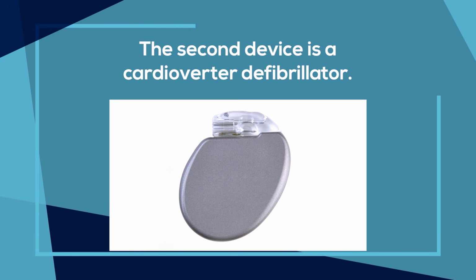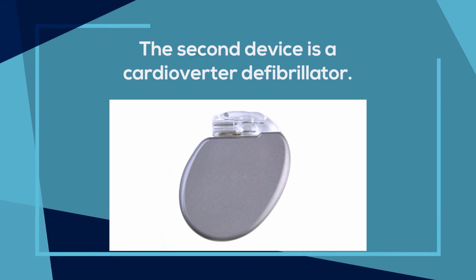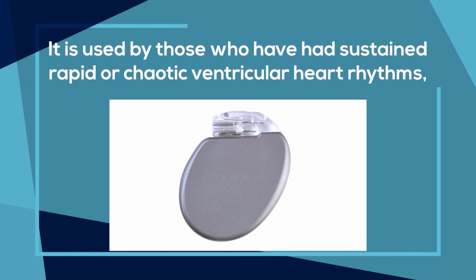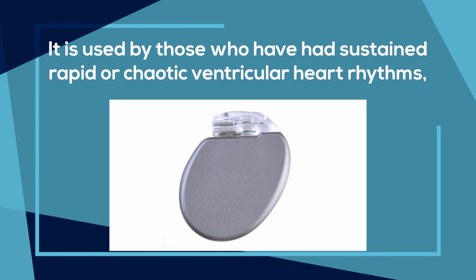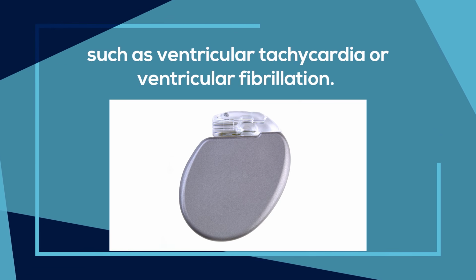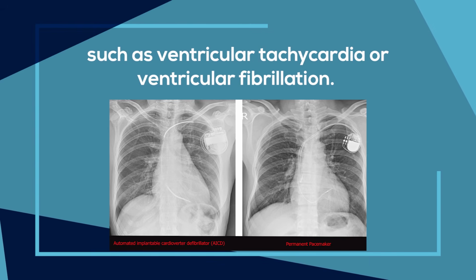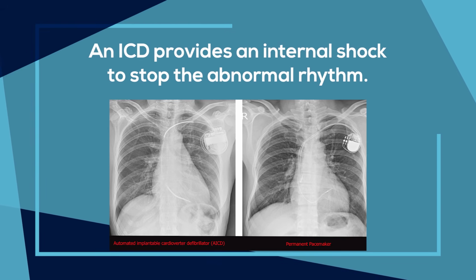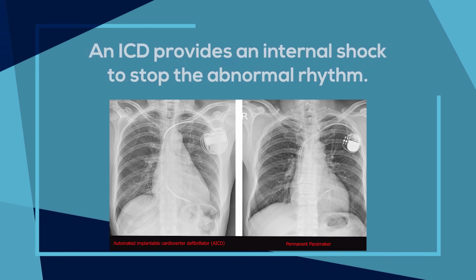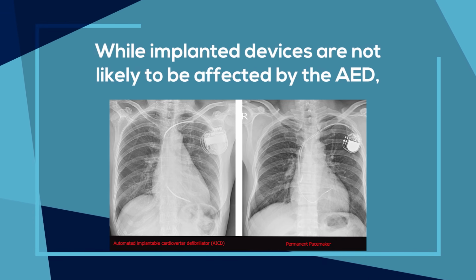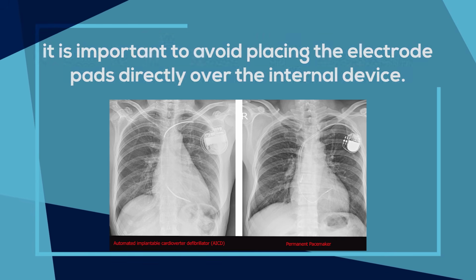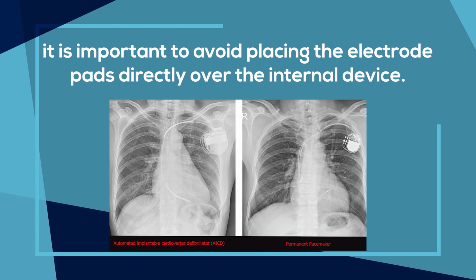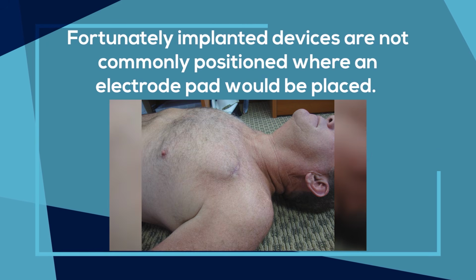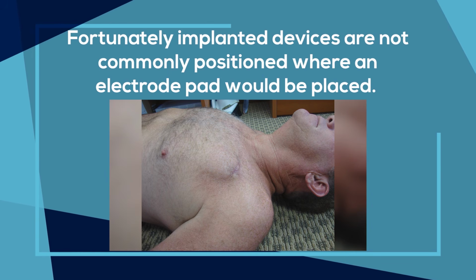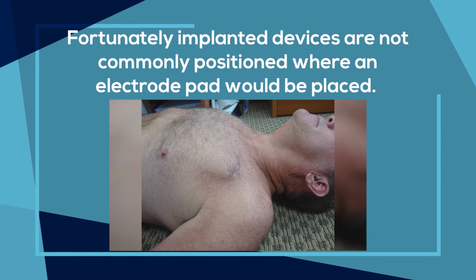The second device is a cardioverter defibrillator. It is used by those who have sustained rapid or chaotic ventricular heart rhythms, such as ventricular tachycardia or ventricular fibrillation. An ICD provides an internal shock to stop the abnormal rhythm. While implanted devices are not likely to be affected by the AED, it is important to avoid placing the electrode pads directly over the internal device. Fortunately, implanted devices are not commonly positioned where an electrode pad would be placed.